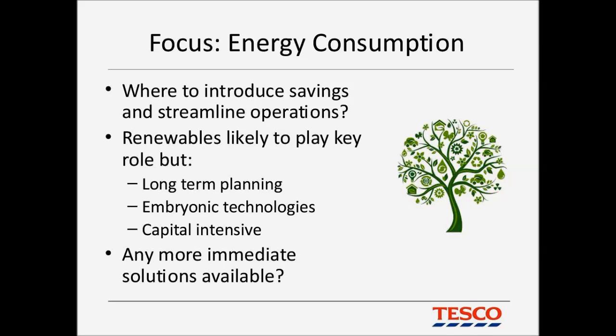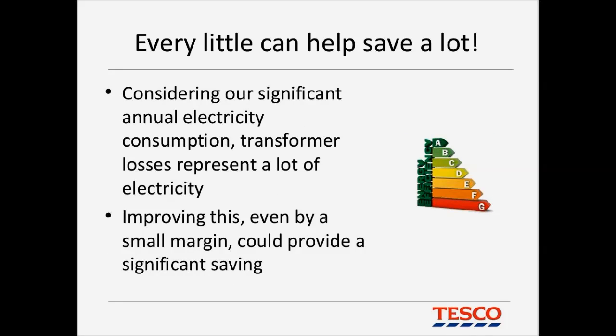Every little helps. It's a good catchphrase and one that we are known for. We run our transformers at high load factor and fairly constant load, so any improvement we can get in regard to losses is worthwhile. Add to this the fact that we have over 1,500 HV sites in the UK, most of which operate 24/7, and the energy benefits are obvious and cumulative.